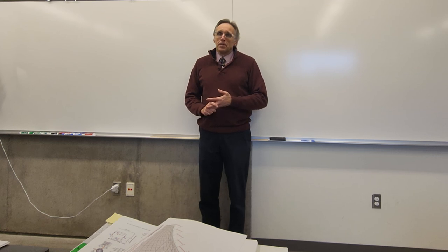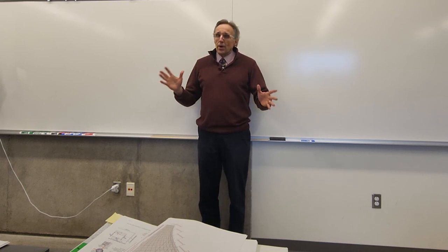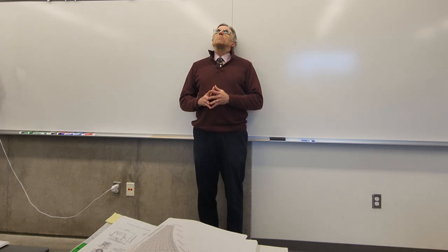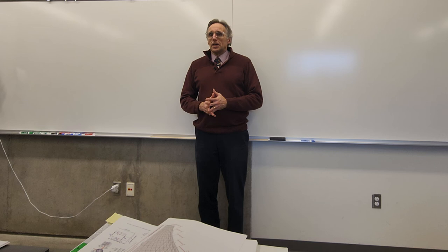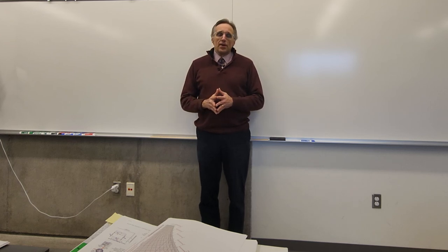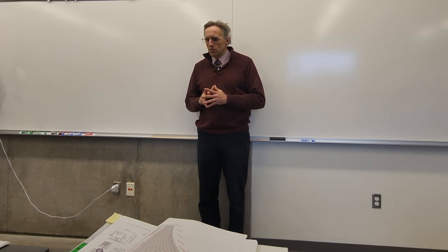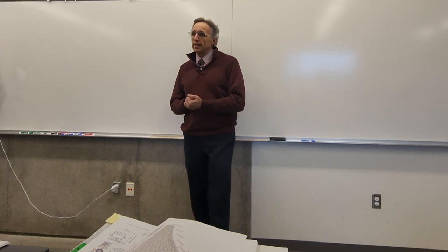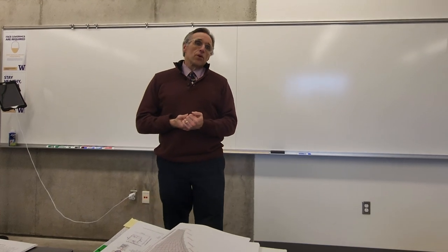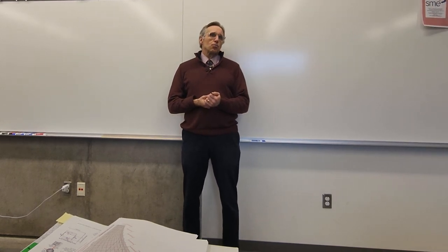And in fact, HCFCs, hydrochlorofluorocarbons, were also phased out, but you can still find those around. You may still be able to get those as replacements for legacy systems, but you can't get them new. So that would be R22. R22 is also very good. But losing R12, that was a big blow to the HVAC industry, because R12 was such a good refrigerant, and you had very efficient, high COP systems. And then we got rid of R22, and we were left with R134A, and R410 is the workhorse for household systems. But R410 is going to have to go away, because it too is a powerful greenhouse gas. And R410 was the last really good one left.